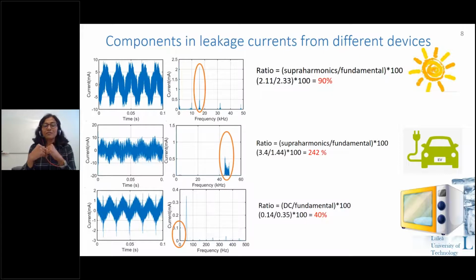Next, we did PE current measurements for several devices, and some of them I have presented here, like the solar inverter in the lab that we were talking about. This is how the PE current looks for the solar inverter. I tried to calculate the ratio of supraharmonic emission in the PE current, or leakage current, from the solar inverter, and it is around 90%. The PE current in steady state is not supposed to have the 50 hertz component, because the system is usually balanced, so whatever comes in through the phase should return through the neutral. But the EMI filters in these devices provide a low impedance path, and hence the supraharmonics end up in the leakage current. They are around 90% compared to the fundamental.